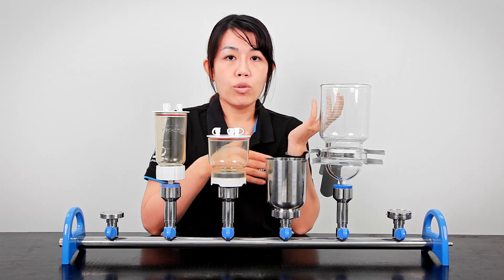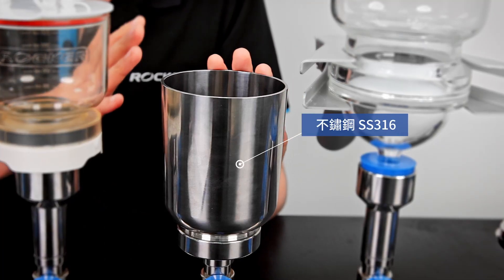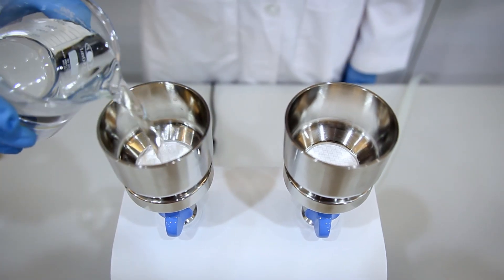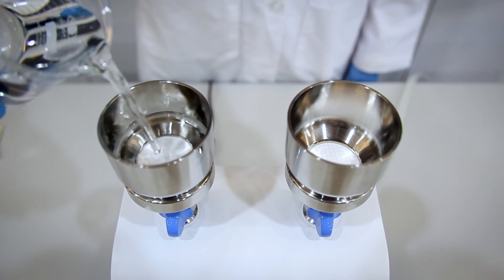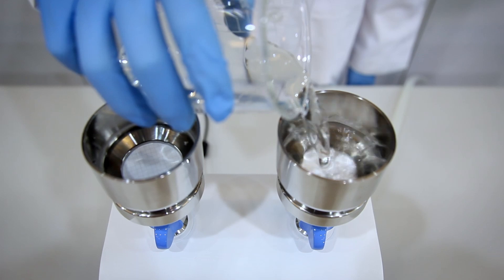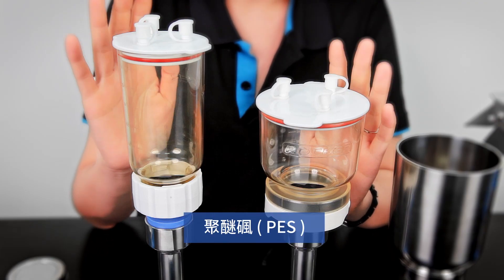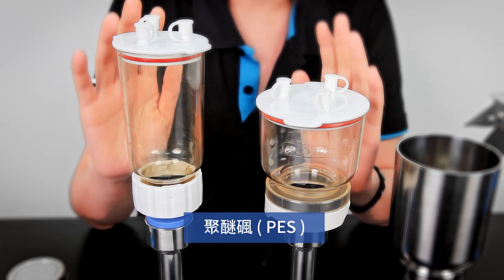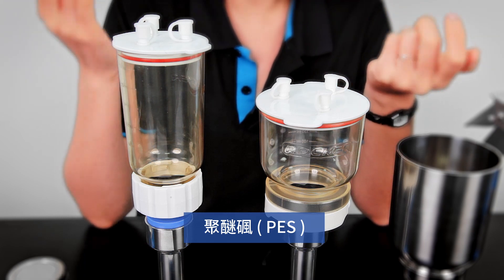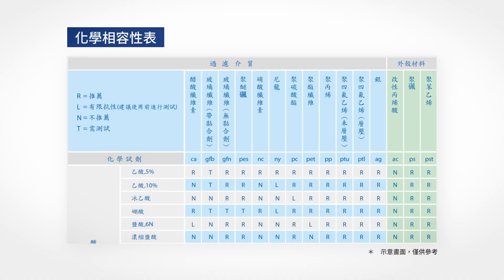But that is not the only choice — we also have the SF collection made of 316 stainless steel, which is highly resistant to alkaline solutions, though as we all know, it may not be ideal for acids. As for the MF and LF, they are made of polyether sulfone, known as PES, and are also resistant to some solvents. If you're unsure, please always refer to the chemical compatibility charts.